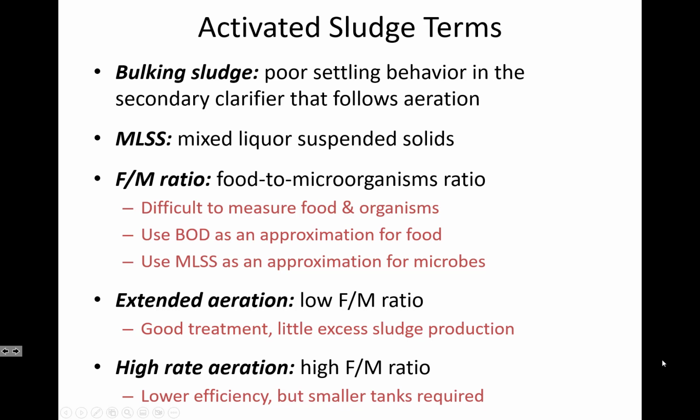And what we usually use is BOD5, which simply is a jar test that says how much oxygen demand is there over the course of a 5-day period. And as you'll see today when we talk about the oxygen demand in the aeration basin, the 5-day test of BOD actually doesn't tell you all of the oxygen demand that there could be. The microbes are going to need more oxygen than they would use in a 5-day bottle test. And so we have to be aware of the fact that that 5-day bottle test isn't the entirety of the amount of oxygen that's really used.